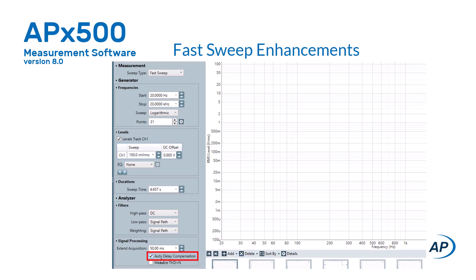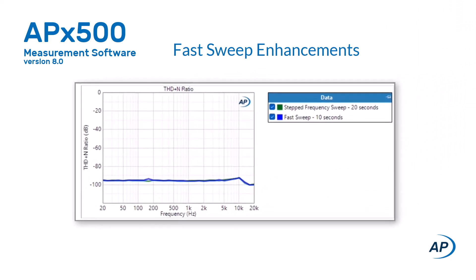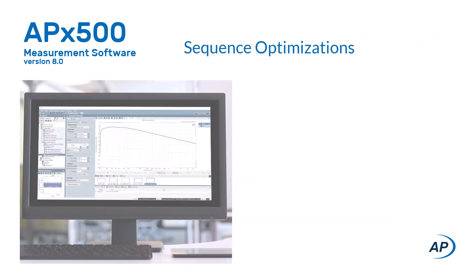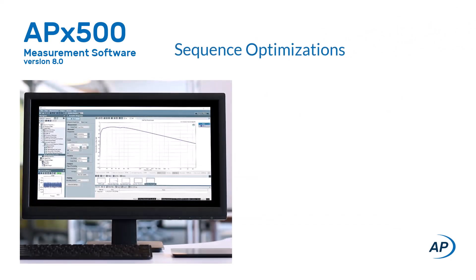Auto delay compensation is selected by default but can be turned off for a known delay and then set manually. For most devices, fast sweep-based measurement of THD+N is at least twice as fast as conventional stepped frequency sweeps. Performance has also been optimized to accelerate sequence execution, improving speed when switching between measurements or adding measurements to a sequence.